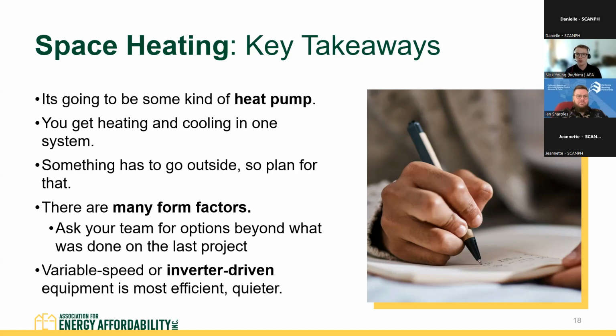Another thing to ask for and look for when specifying systems is variable speed or inverter-driven equipment. That's going to be the most efficient, and quieter, because it can ride the demand coming from the building, instead of turning on at max capacity and then turning off. Equipment that can vary its capacity and run at 30 or 40% capacity will run efficiently for longer periods, which is better for your equipment long term - lower maintenance, longer equipment life, things like that. So recommend variable speed equipment when you can get it.